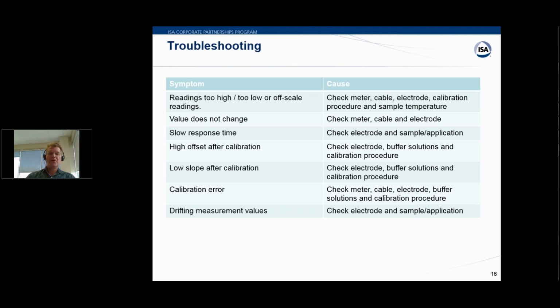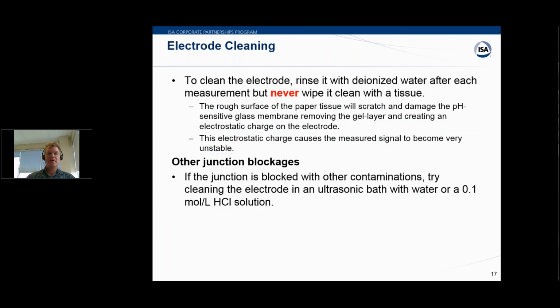Just for summary, if your readings are off, it's almost always check your meter, your cable, and your electrode. Those are the typical things. Remember, we have an electrical circuit, so we just need to check the different pieces of the circuit to make sure that they're all working properly. The causes on the right are very common, but some of the symptoms that you can see are poor response, offset, slope, calibration error, and drifting. So just keep these things in mind.